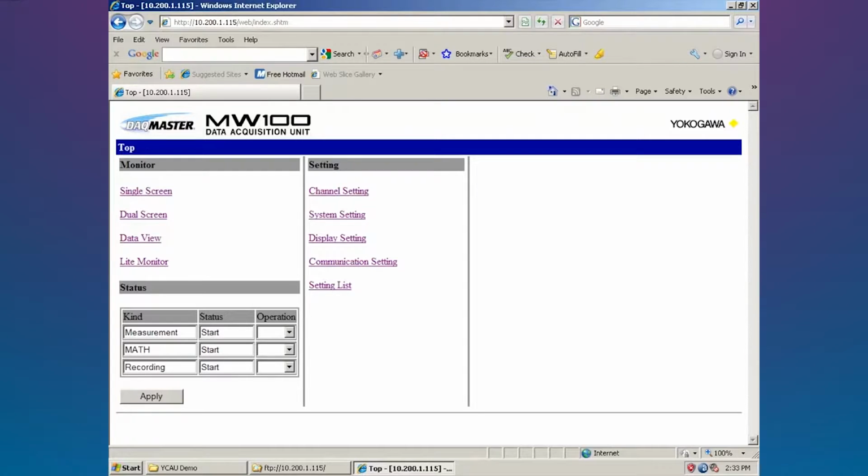It supports up to 2 gigabytes of compact flash storage and has a good operating range of -20 Celsius to +60 Celsius. It also offers built-in Ethernet and optional RS-232 or 485 serial interfaces. Locally, it can have up to 60 channels, and up to 300 remote points can be brought in via communications. Sample times can be as fast as 10 milliseconds for up to 10 channels, and we can also do 1 second for all 360 channels.